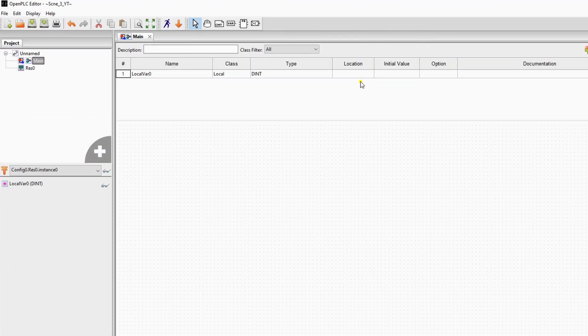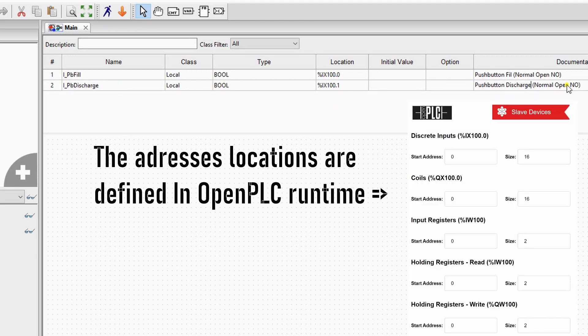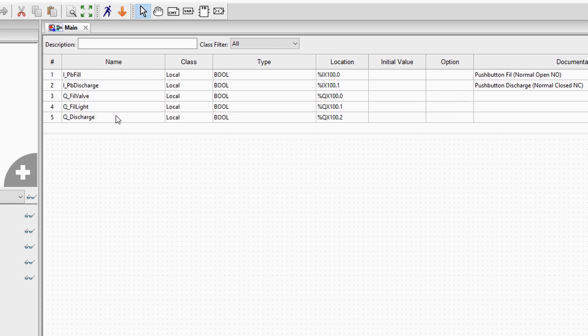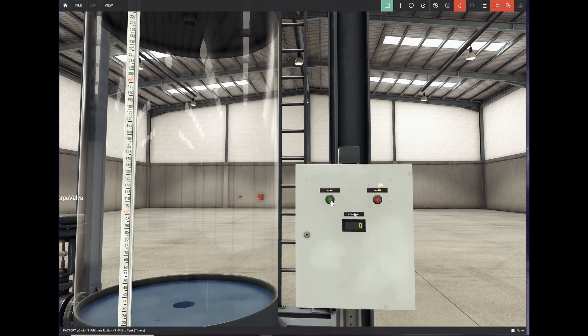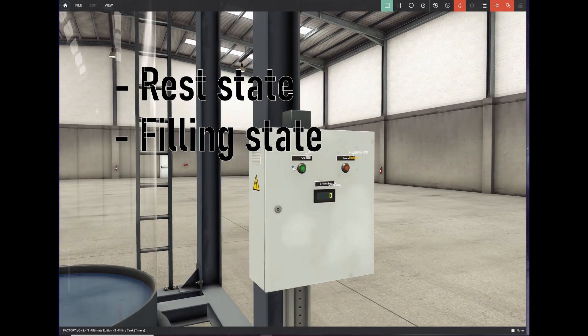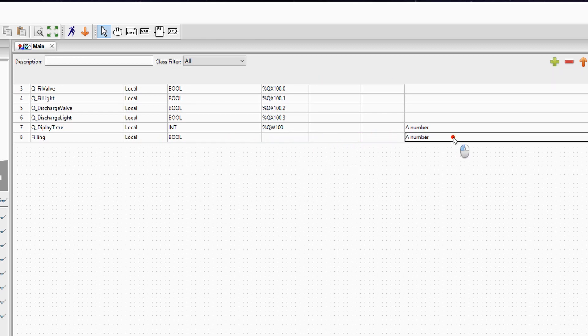First off, we open a new project and start to declare our input and output variables, the same as we did in Factory IO. Before we start programming, I would look at the process of the machine and the states it could be in. The machine can be in 3 states: doing nothing, in the filling state, or in the discharging state. I create two variables of the type bool for the state, one called filling and the other discharging. I don't bother to make a variable for doing nothing, because you don't have to set any outputs for it.